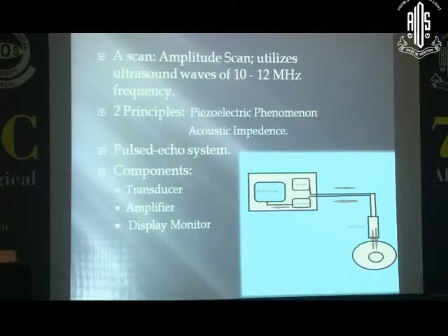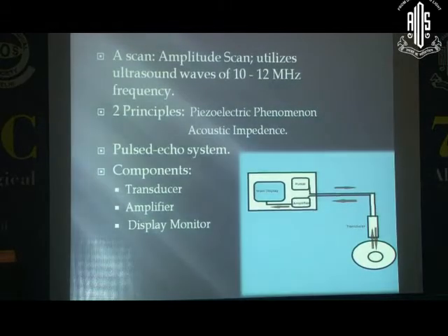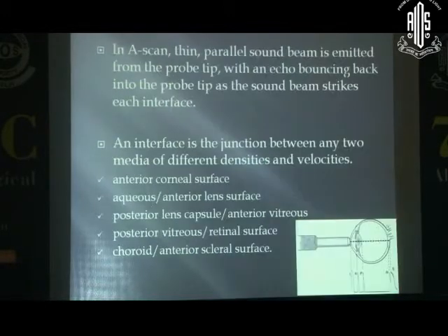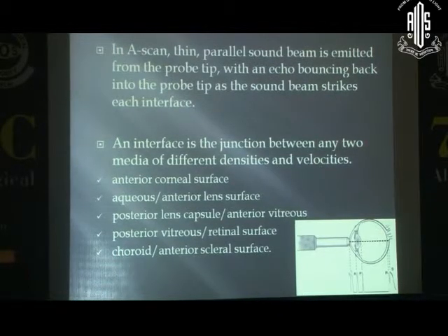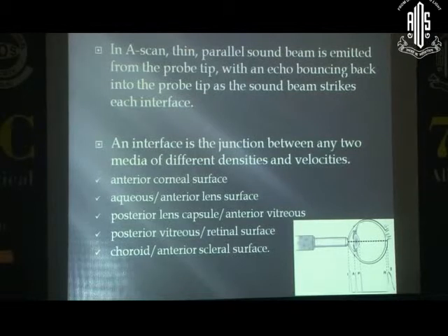The A-scan biometry mainly works on the principle of piezoelectric phenomenon and acoustic impedance. You have three components: the transducer, the amplifier, and the display monitor. What an A-scan does is a thin parallel sound beam is emitted from the probe with an echo bouncing back into the probe, and then the sound beam strikes the interface.